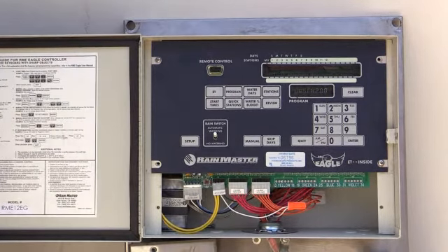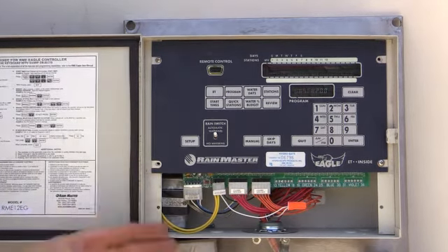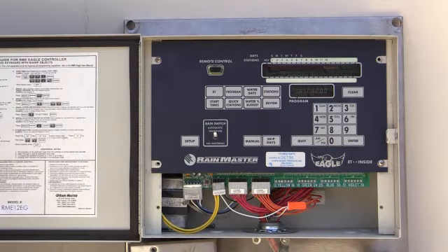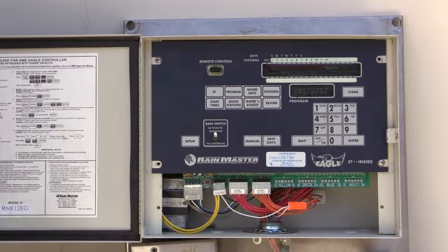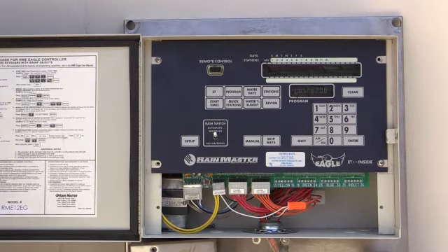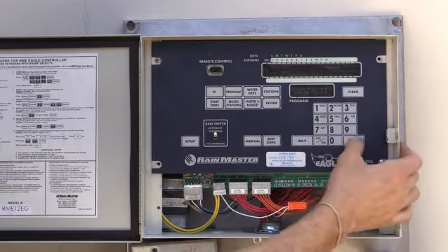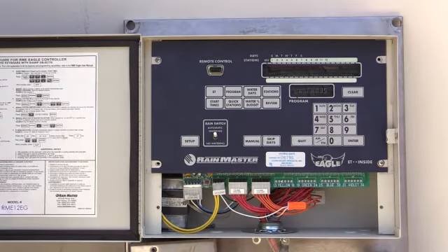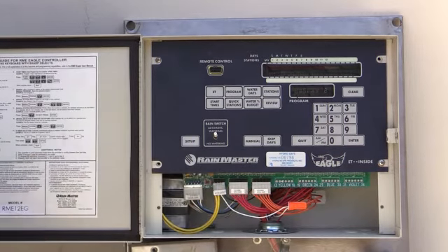Unscheduled flow is basically just that. It's when the timer's saying, hey, I'm not supposed to be on, but we have flow going through our piping system. Now this is set at 200 gallons per minute. Again, that's very, very high. In case you have someone that uses quick couplers and gets access to the water during the day when we're not irrigating, you might want to set it. So for a 3/4 inch quick coupler, if we put 35 gallons per minute, we're well below that. So we're good.